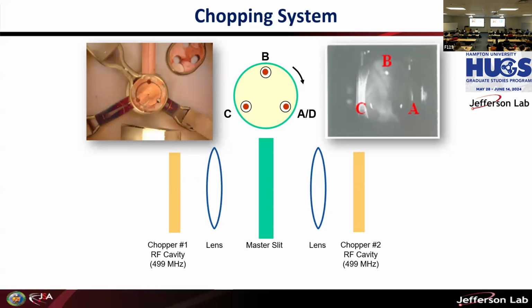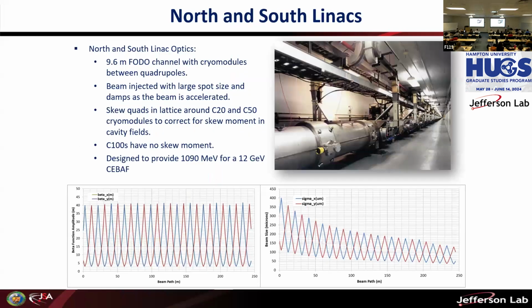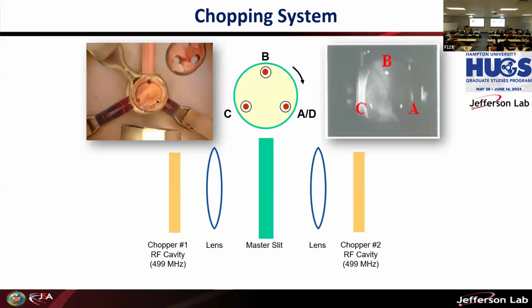It's a copper thing. So A, B, C, D, and we have a viewer where you can actually see. So those are real beams, right? B, C, A, and you use that to... Not shown in this picture, on the back of that thing, there is some mechanical device called slits that you can insert. They are V-shaped, and you can insert them up or down to restrict the amount of electrons that are coming out. So that's how you control the beam intensity.